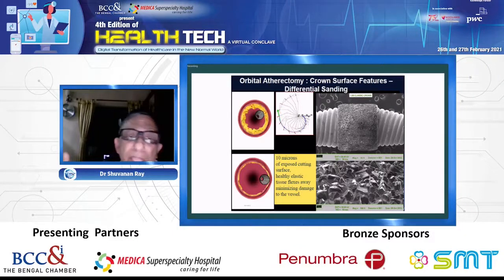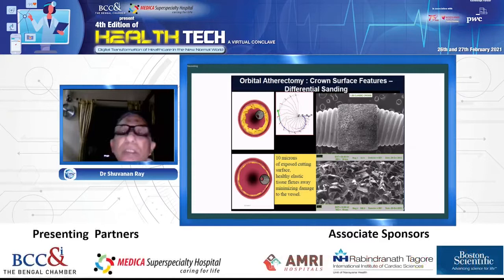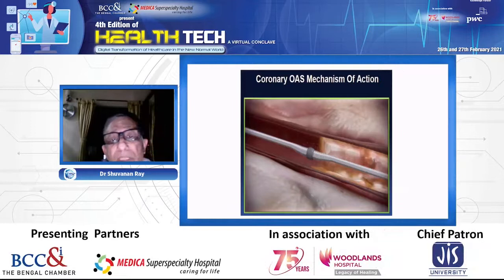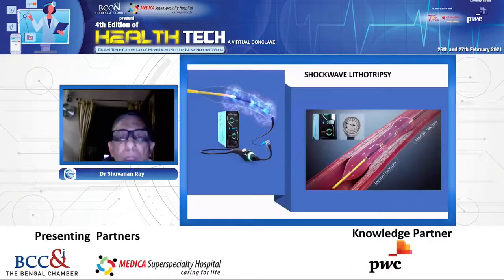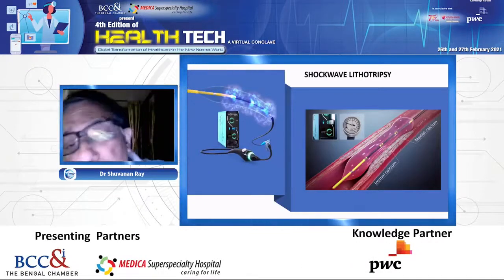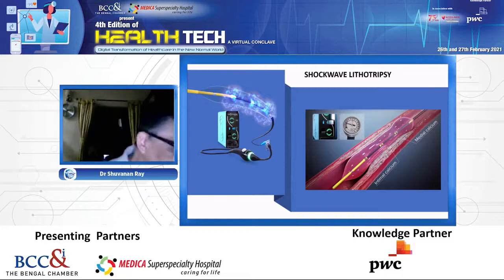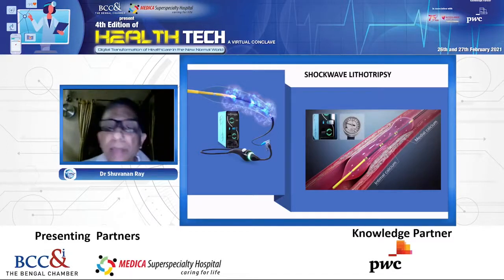So there are two important points. Rotational atherectomy moves around with a rotation. Orbital atherectomy moves in an oblique way and acts as a jackhammer. Here, the microns or particles are larger, around 10 microns, whereas in rotational atherectomy, in ideal cases, the pulverized particles are much smaller, less than 5 microns. You can see this - this is an index finger with a ring, and this finger, when it moves in an oblique way, acts as a jackhammer and breaks the calcium.